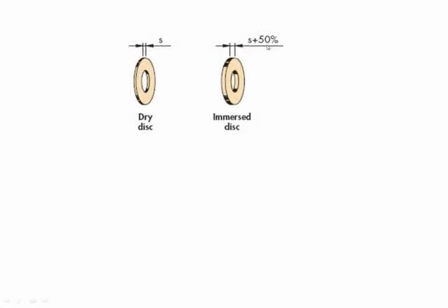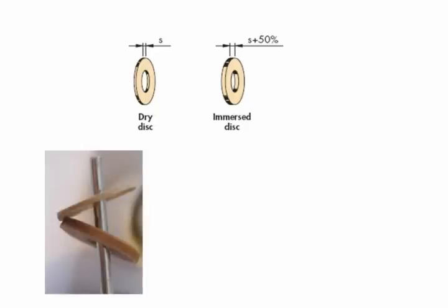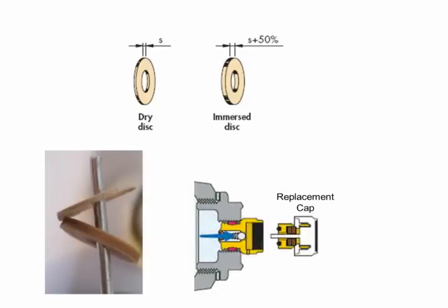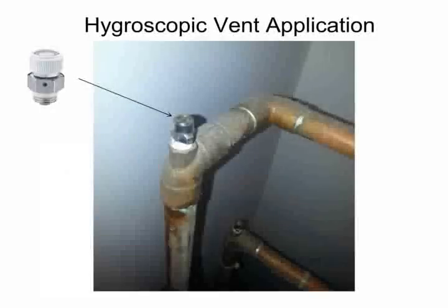They also can be operated in a manual mode by just spinning this cap counterclockwise. Here's a shot of what that dry disc looks like, these series of discs, these sponges, and then as they get wet, they expand quite a bit. And Hot Rod in the earlier training webinar showed a dry disc and a wet disc to show you that phenomenon. And if they ever need to be replaced, the nice thing is there's a built-in check valve here, so you can spin the cap off and within seconds literally replace that cap.